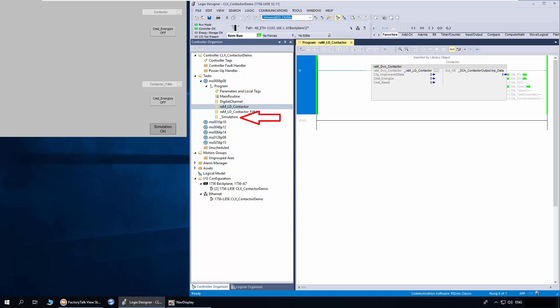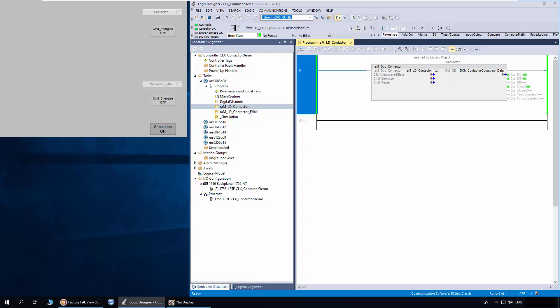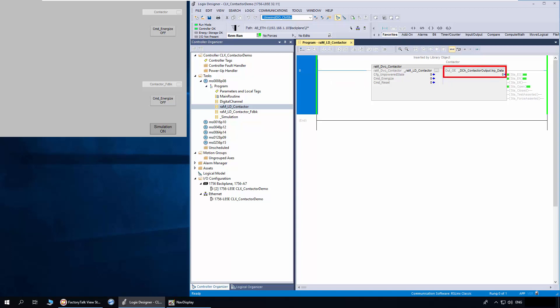The simulation routine has code to simulate contactor auxiliary feedback. The contactor object is used for controlling a contactor with no feedback. The contactor is commanded to open and close from user logic using the command energize parameter. The reset command is to reset the addon instruction error status.